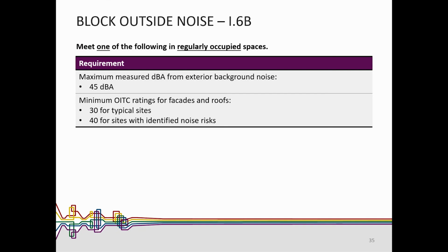Going through one by one, back to non-learning spaces: we have two options for measuring the dBA from exterior background noise, with a threshold of 45 dBA. This happens post-construction but pre-occupancy, in regularly occupied spaces, with mechanical systems turned off, to ensure you're only capturing noise coming from outside.